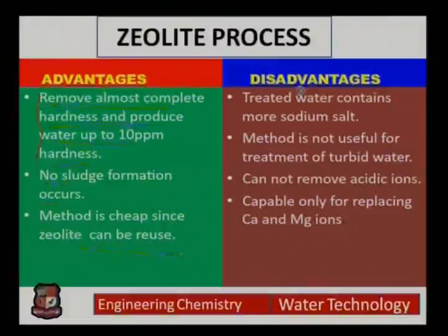So whenever turbidity is present in the water, this turbidity may clog the pores of zeolite, and hence zeolite cannot be used for further softening process. So if turbid water is there, we need to make sure to remove the turbidity prior to softening. Otherwise zeolite softening will not occur at all and zeolite would be wasted. So turbid water, a strict no-no.